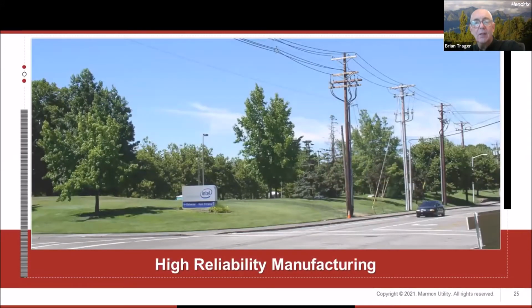So starting with our high reliability applications, these are, again, where you're making semicon chips. Here's one of the facilities in the state of Oregon. They can't have outages, so they have to have multiple feeds. Even if you have a voltage dip for 5 seconds, you're going to reject $1 million worth of one lot of semicon chips. So they have to have high reliability. They can't have even momentary trips on the breakers.